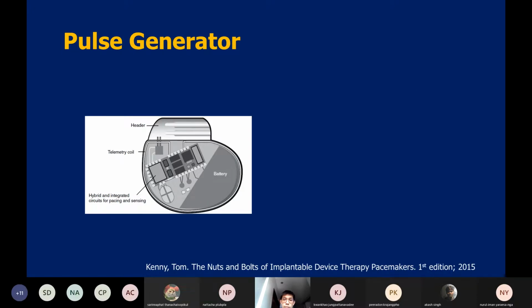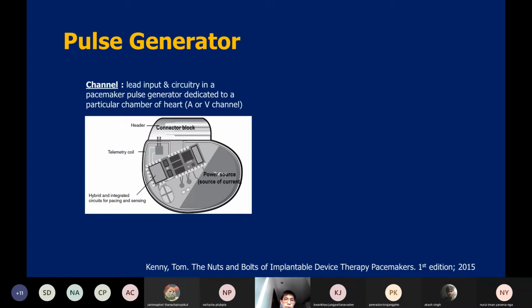This is the pulse generator. There are many parts of the pulse generator, one of which is the header. The header is the part we use to connect to the leads. We put the leads into the channels of the pulse generator. If it is a dual chamber pacemaker, the upper channel is the atrial channel, and the lower channel is the ventricular channel. On the right side, the dark gray part in the picture is the battery. This battery lasts around 8 to 10 years, depending on the patient's usage. There is also the circuit which controls the pacing and sensing function of the generator.